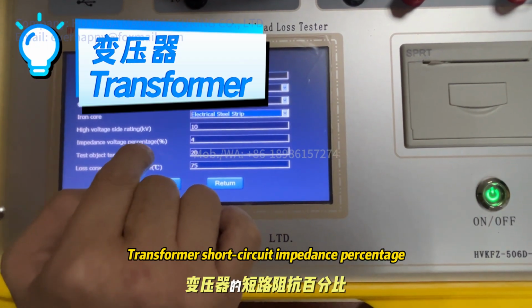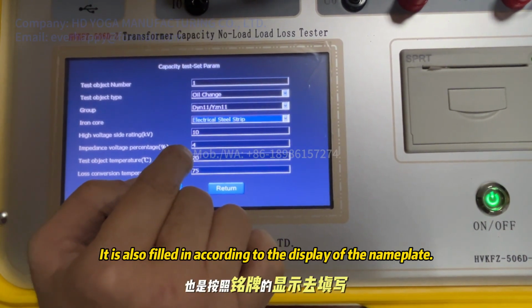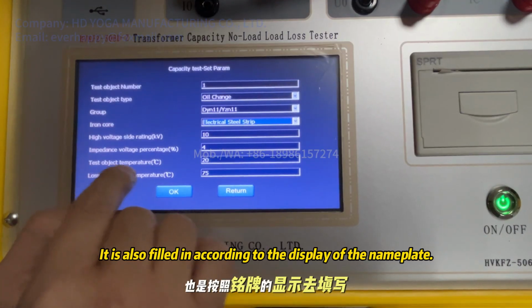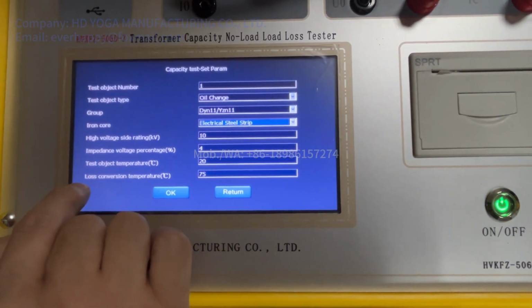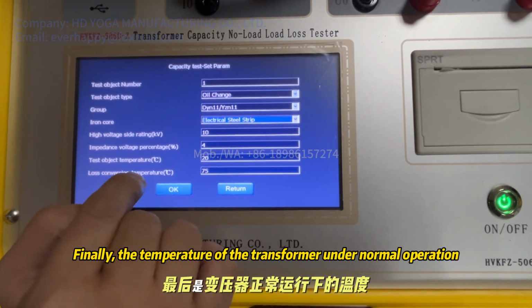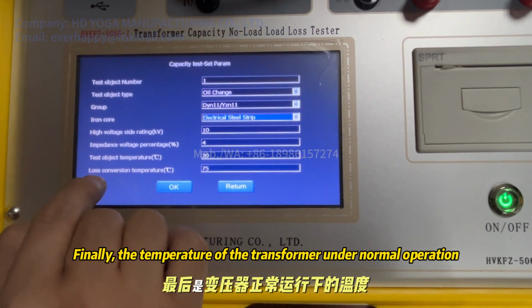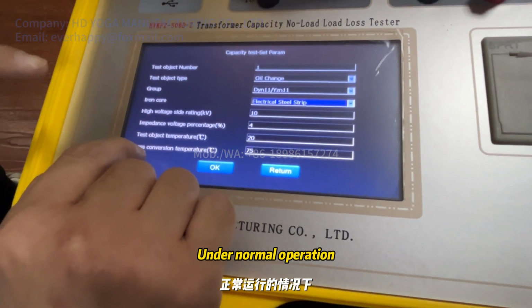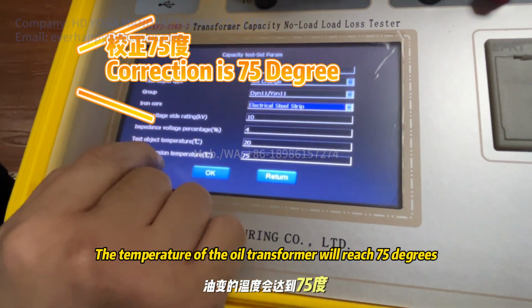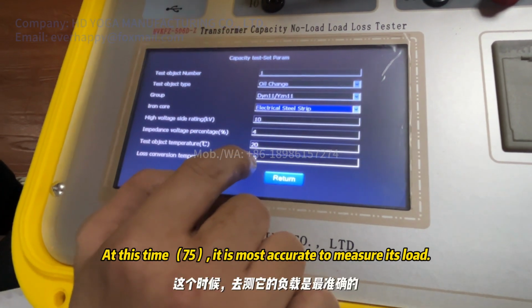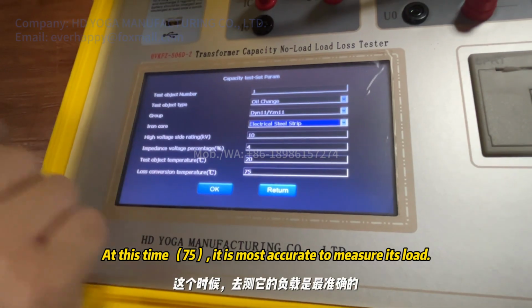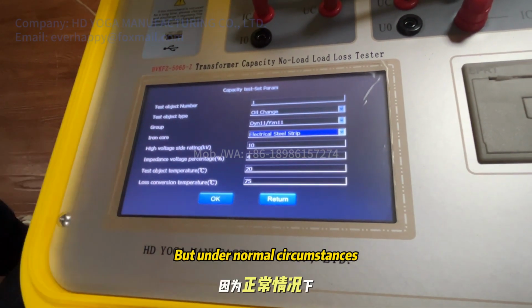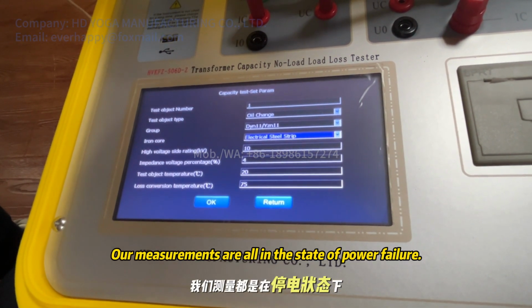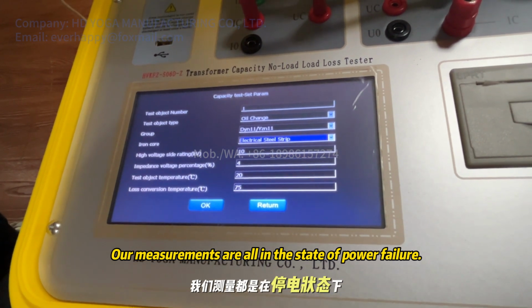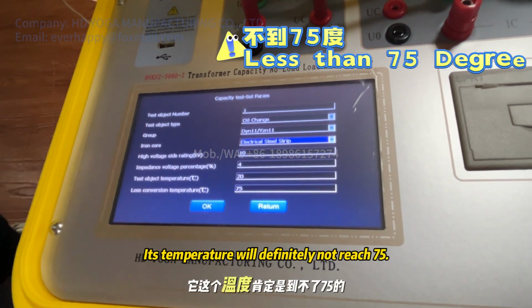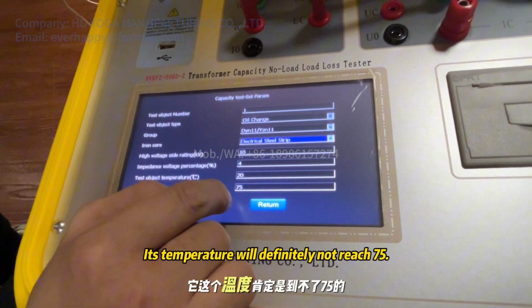Transformer short circuit impedance percentage. It is also filled in according to the display of the nameplate. Ambient temperature. Finally, the temperature of the transformer under normal operation. Under normal operation, the temperature of the oil transformer will reach 75 degrees. At this time 75, it is most accurate to measure its load, but under normal circumstances, our measurements are all in the state of power failure. It's not running inside. Its temperature will definitely not reach 75.